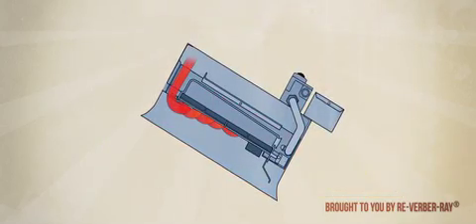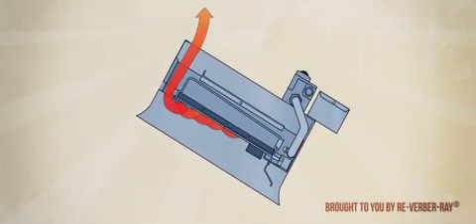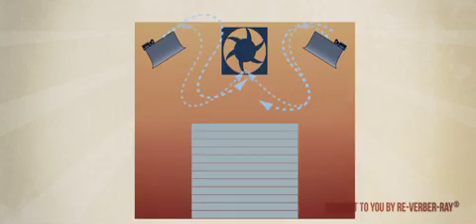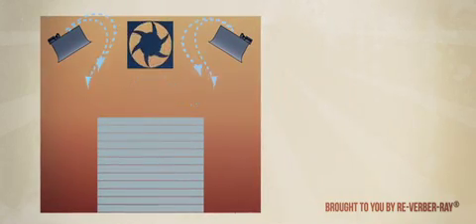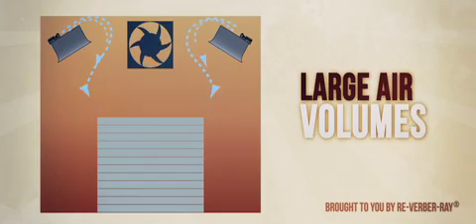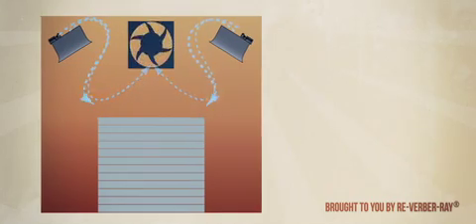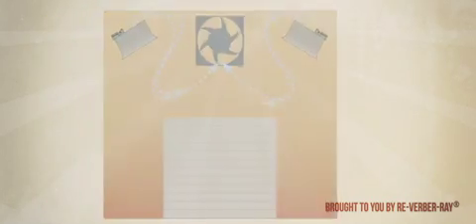As a direct-fired appliance, high-intensity heaters cannot be directly vented and require adequate, indirect building ventilation. As a result, heating an overall area with infrared heaters is particularly suited for buildings with large air volumes or high rates of air movement where air heating methods are grossly ineffective.